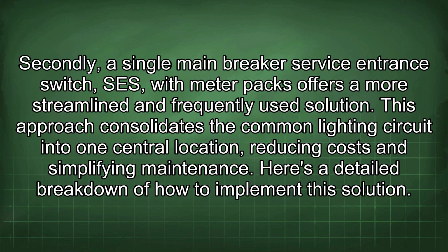Secondly, a single main breaker service entrance switch, SES, with meter packs offers a more streamlined and frequently used solution. This approach consolidates the common lighting circuit into one central location, reducing costs and simplifying maintenance. Here's a detailed breakdown of how to implement this solution.